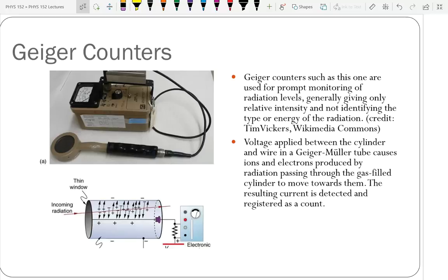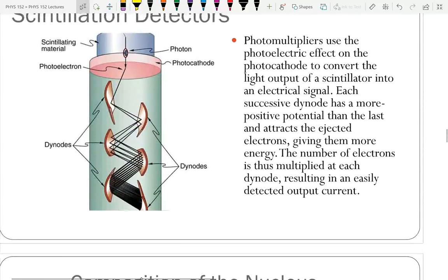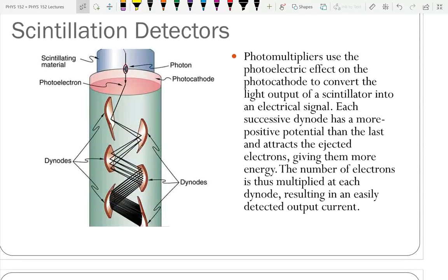So the scintillation detector has a window on it, and when radioactive particles come into the window, it will excite electrons, they'll fall back down and give off light. And that light is the scintillation, and then that light signal is what is detected. They have light amplifiers, things we call photomultiplier tubes in there, that use high voltage. So this is actually what they have.